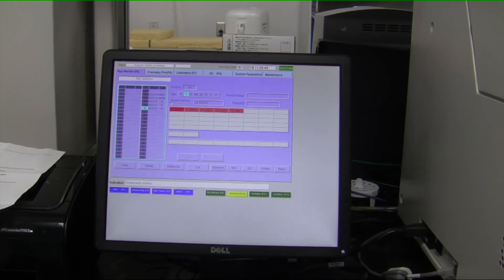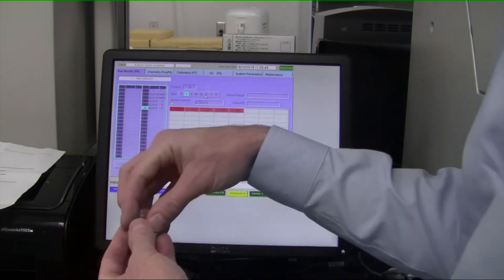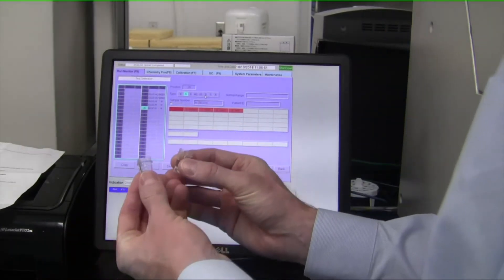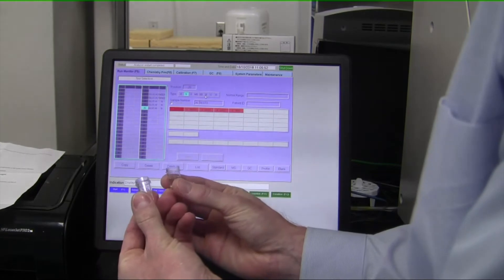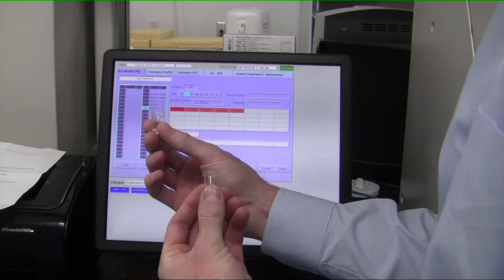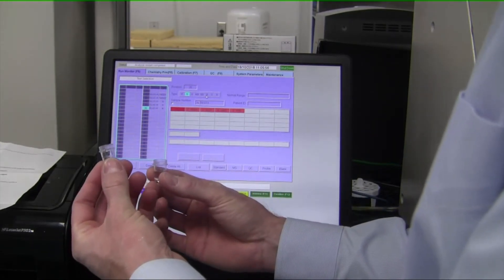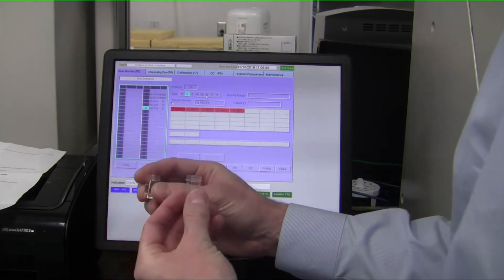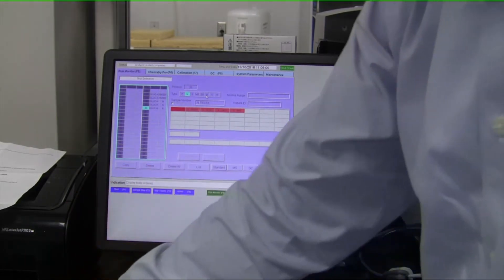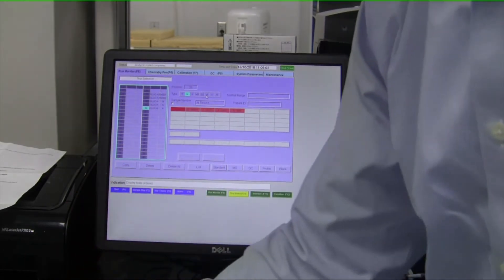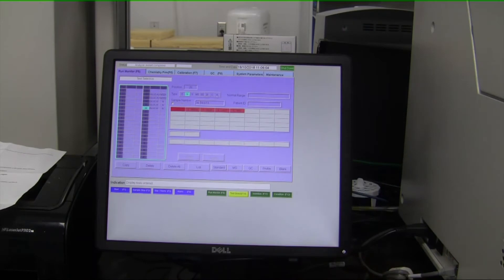So it automatically names the samples. It increases the number by one digit. If you wanted to change that, you could of course just type it in. And then here are the sample cups that are used—this is your basic sample cup. This is going to be your deionized water. I'll put some of the calibrator material in here for the two positions, and then we'll load on positions number 24, 25, and 26 with sample cups of unknown concentration, and those are going to be tested for glucose.